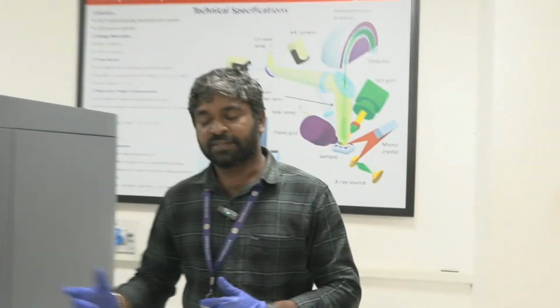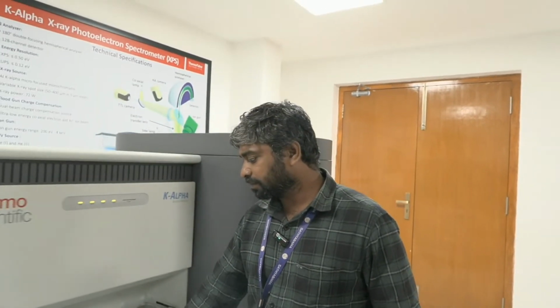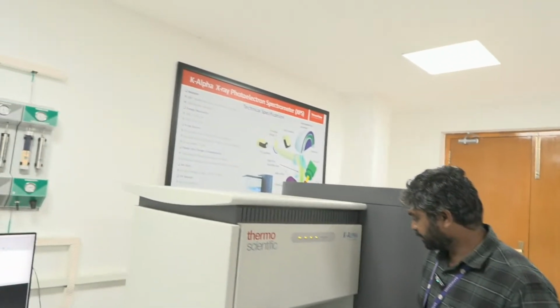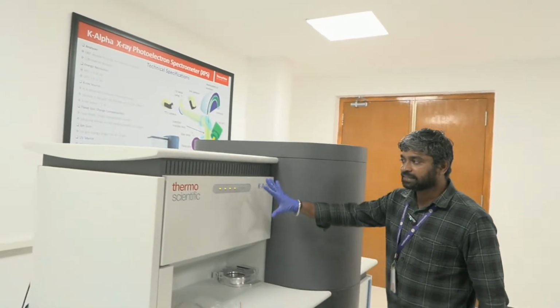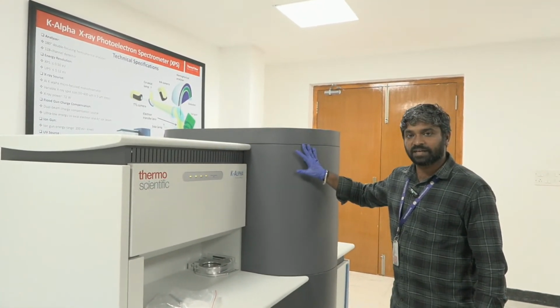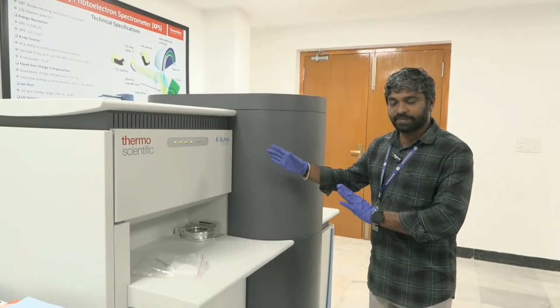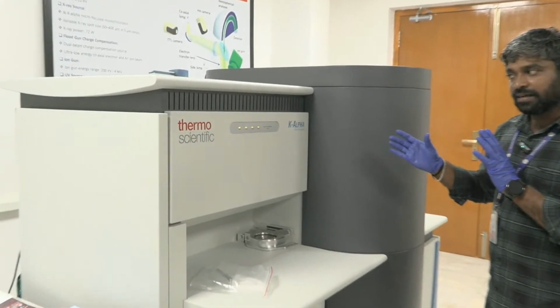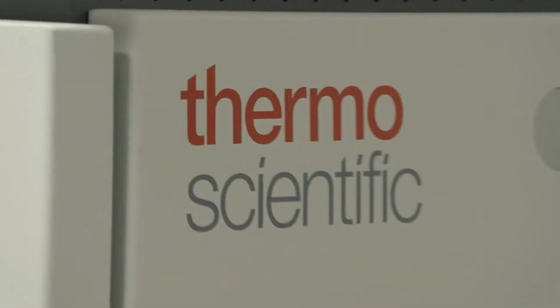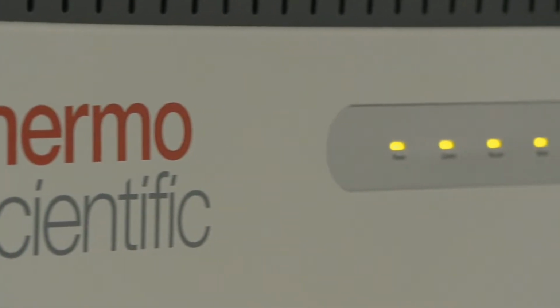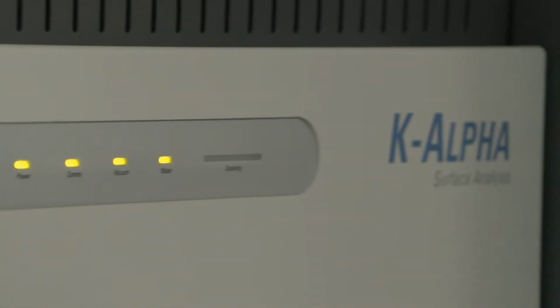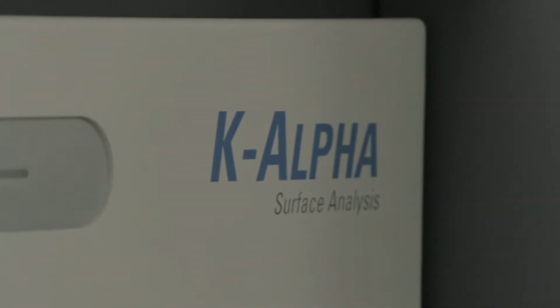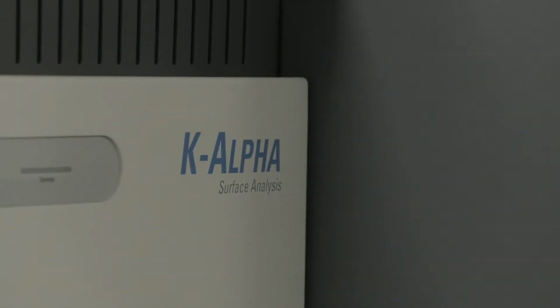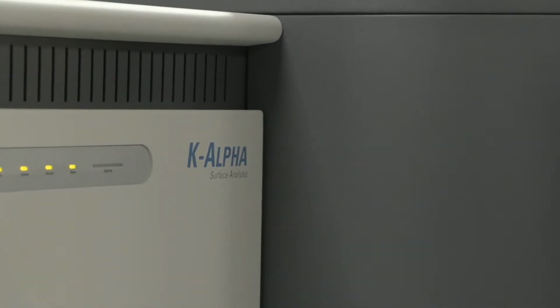So now we will go to the instrumentation part. So here, this is the Thermo Scientific K-Alpha model, and this XPS system not only does XPS, here we also have the UPS options. In XPS we will use the X-ray source. In UPS we are using the ultraviolet radiation.